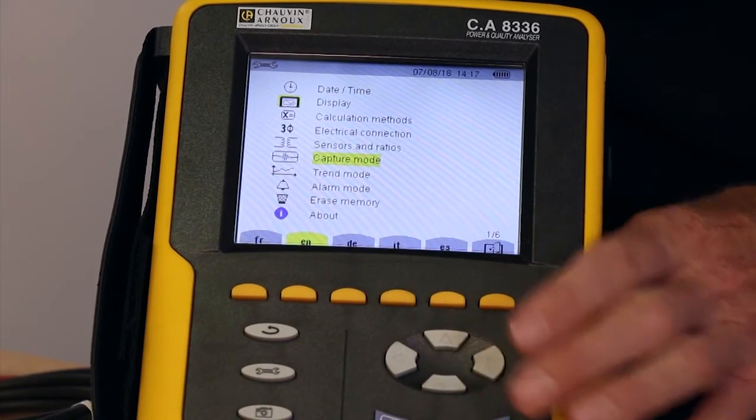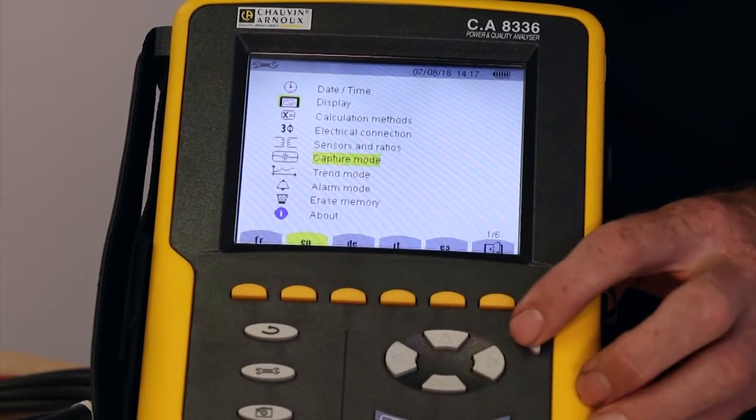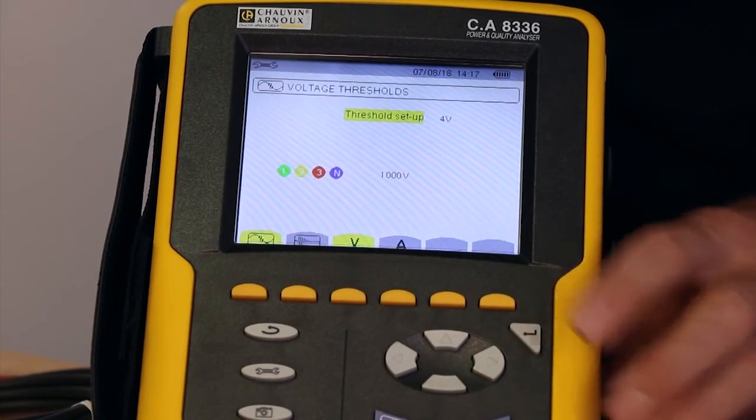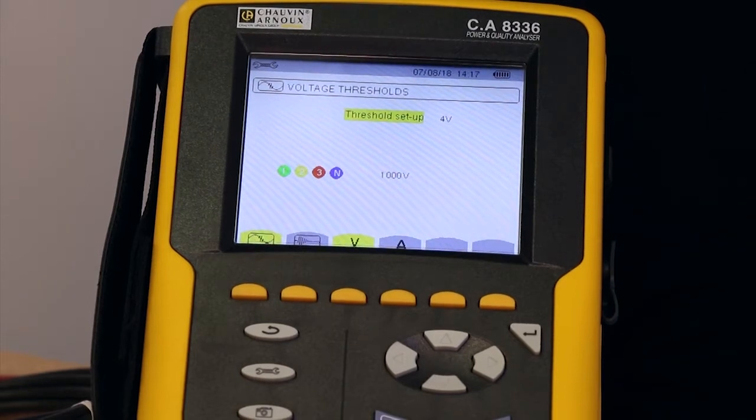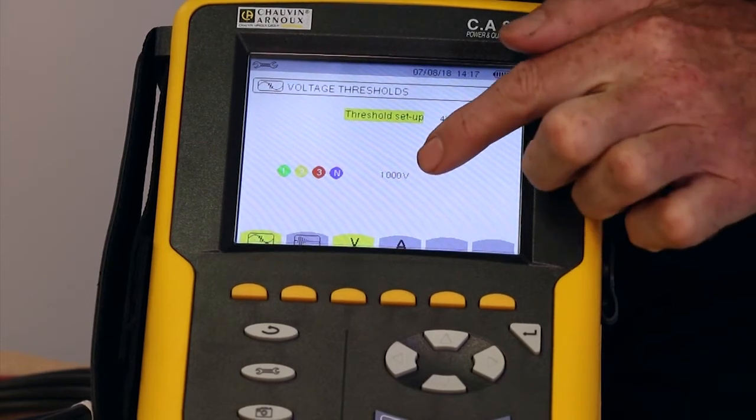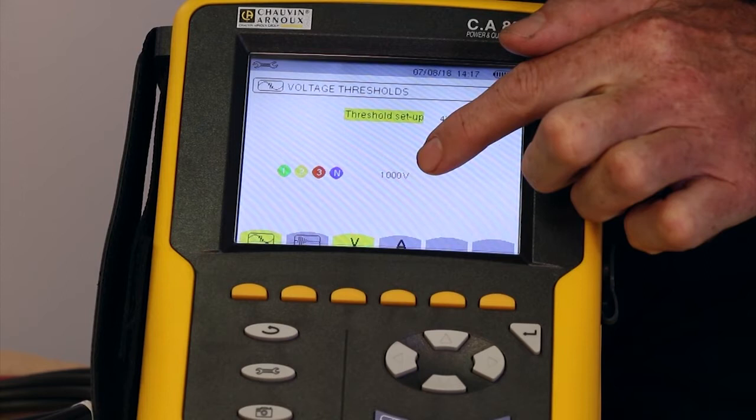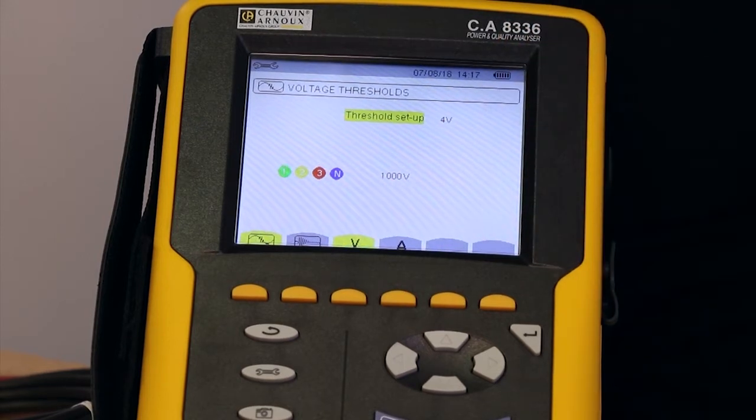The next key position down allows us to set a threshold for transients. This is called capture mode. In other words, when recordings will be triggered by an over-voltage, the level of which is decided by the user. I can select any level I want. So here I'm selecting to see only transients that are above 1000V.